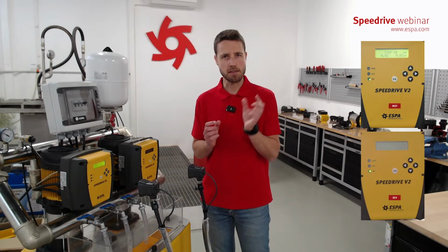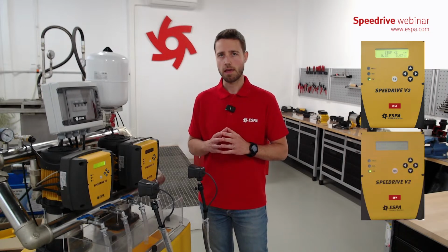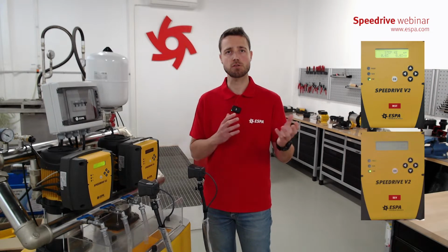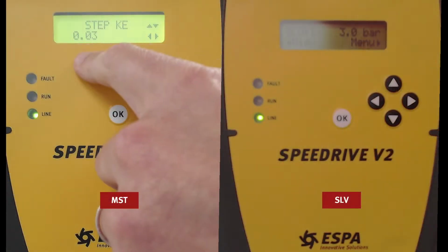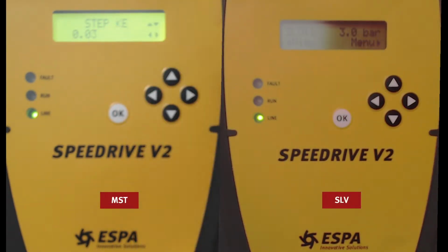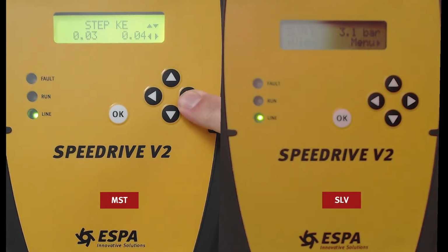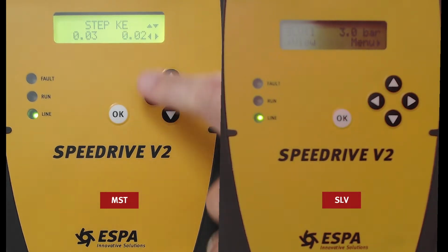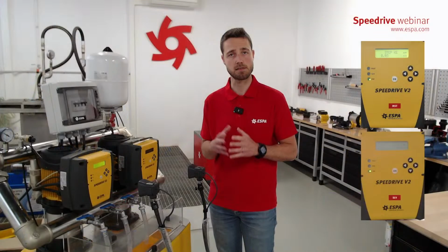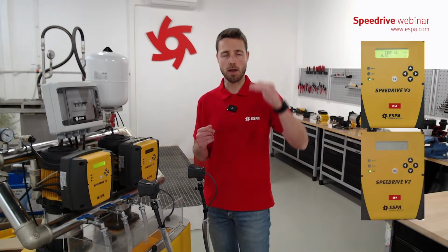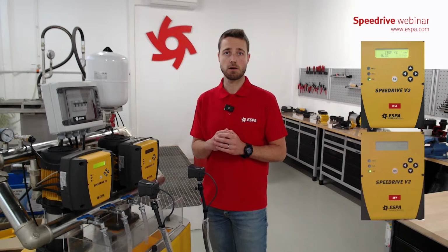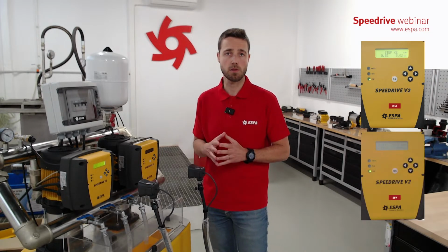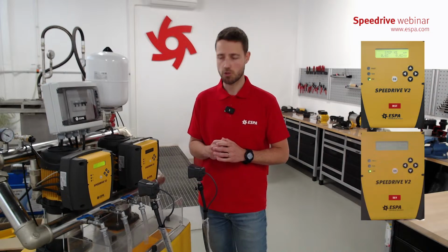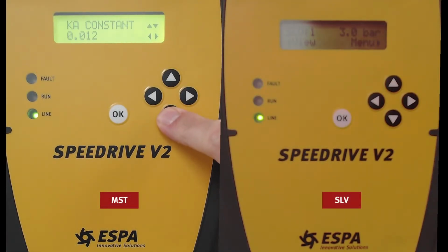What is the step? This is just the frequency of reading. How often does a transducer read? So every 0.03 milliseconds. If we press, for example, 4 milliseconds, it will go slower. If we press and we go to 0.02, it will go faster, but it's the same. The faster we go, maybe we have more oscillations, and the slower we go, the system is probably more balanced, but it will go too slow to reach the desired duty point. A step for the wide band.